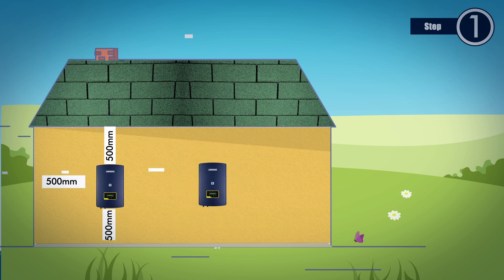If more than one inverter are to be installed together, a minimum of 500 mm clearance distance should be kept between the two inverters.